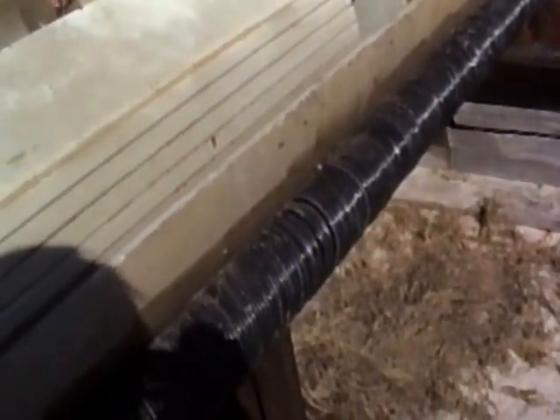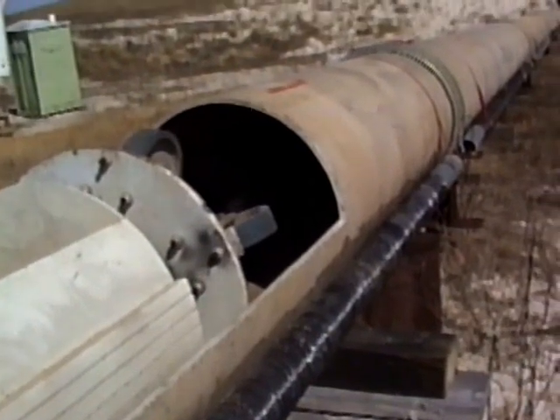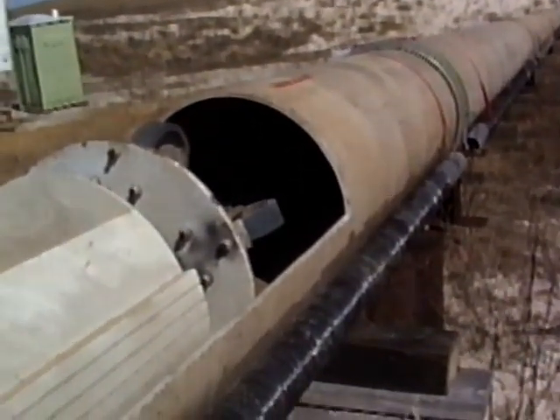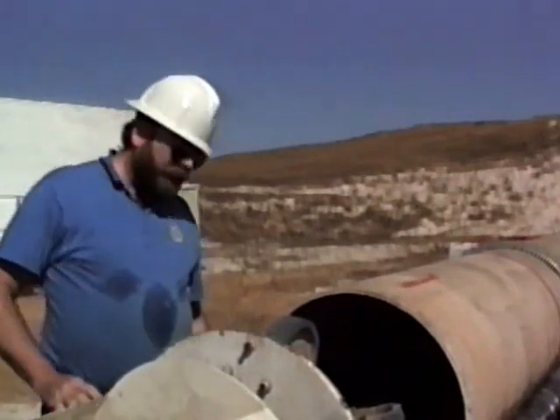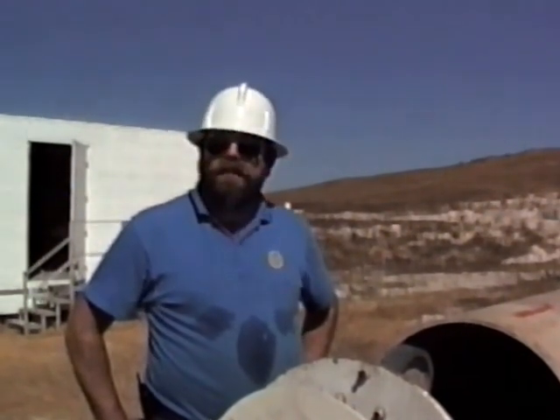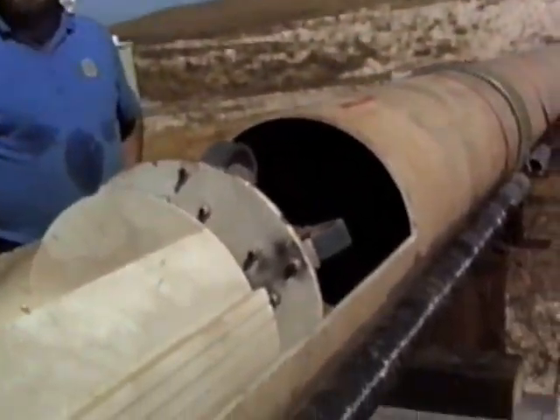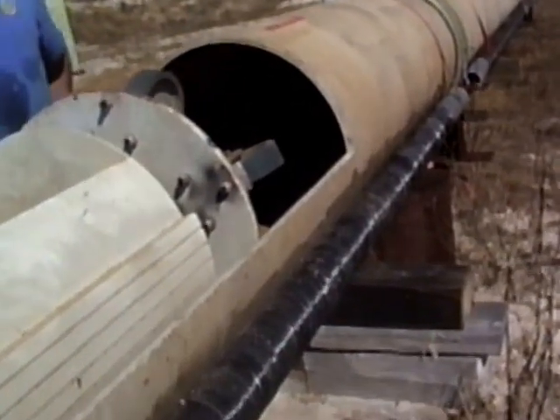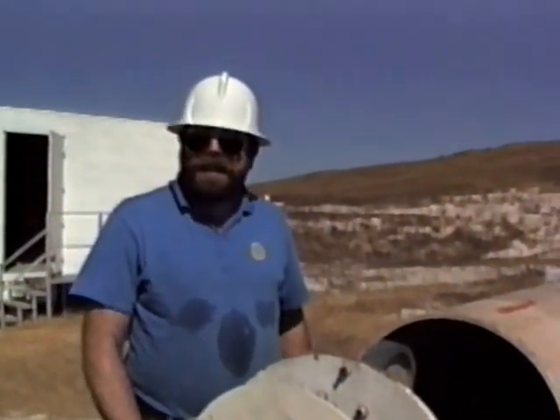The windings are made out of what's called direct burial cable — ordinary wire with very strong insulation so that it can withstand ultraviolet light from the sun, rain, and so forth. It's perfectly legal to bury this cable directly in the ground. We chose this cable because for a mining application the motors would be subjected to quite a bit of wear and tear, and we wanted them to have a long life. The winding of this motor is done in a somewhat complicated way, but the complication is offset by the advantage that there are no joints in our windings. There's about 3,000 feet of wire wound in three continuous pieces — it's a three-phase motor with no joints at all. Had we used the simpler winding, we would have had over 200 joints on every single motor, sitting out here in the sun and rain.